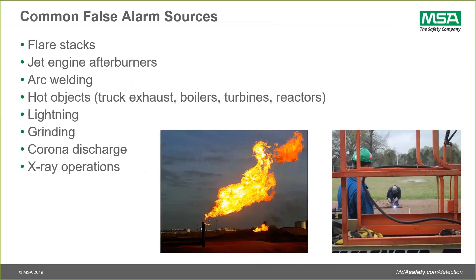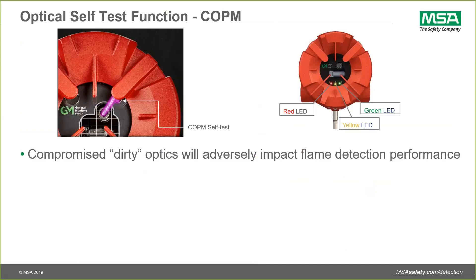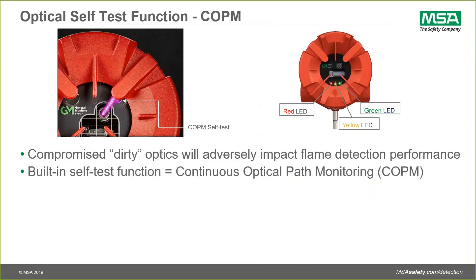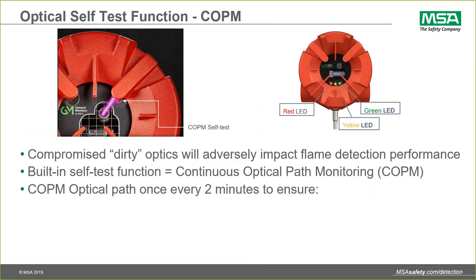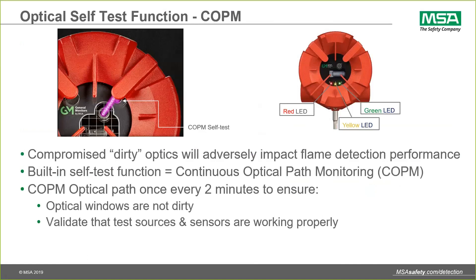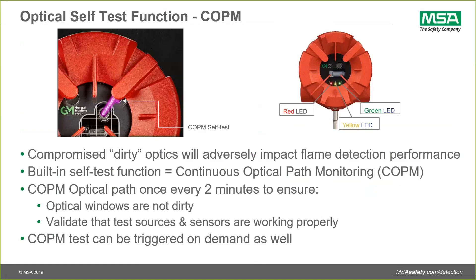Another important attribute to require on your flame detectors is a self-test function, because compromised or dirty optics will adversely impact any flame detector's performance. They are optic devices — if they have a dirty window, they're going to be compromised. Our type of testing is called Continuous Optical Path Monitoring, or COPM — it's a built-in self-test. The microprocessor energizes a small built-in lamp once every two minutes to validate that the windows are not dirty, that the test source is functioning properly, and that the sensors have adequate sensitivity. We also support a test on demand, so end users can trigger it manually even though it is testing itself every minute or two.